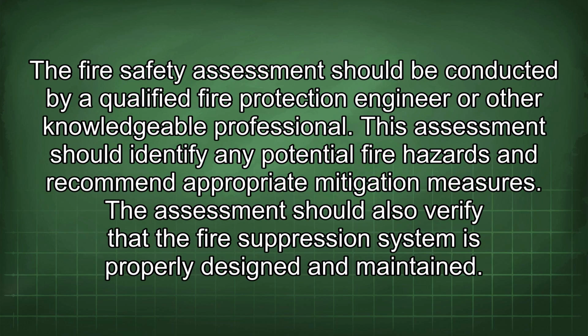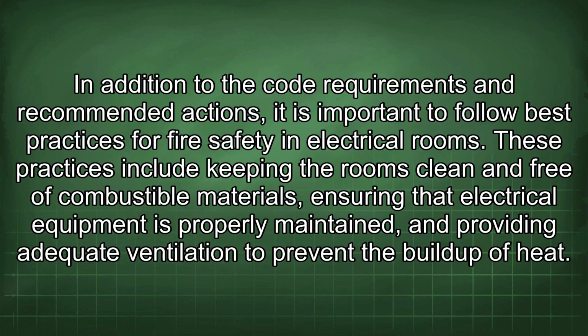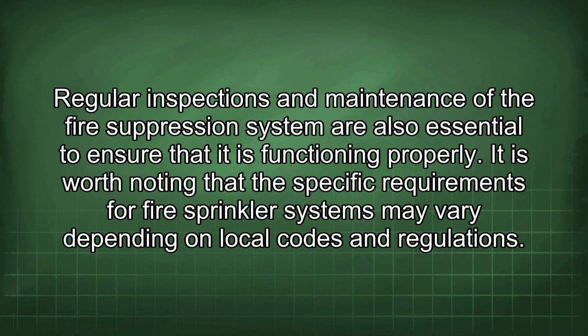Fire safety assessment should be conducted by a qualified fire protection engineer or other knowledgeable professional. This assessment should identify any potential fire hazards and recommend appropriate mitigation measures. The assessment should also verify that the fire suppression system is properly designed and maintained. In addition to the code requirements and recommended actions, it is important to follow best practices for fire safety in electrical rooms. These practices include keeping the rooms clean and free of combustible materials, ensuring that electrical equipment is properly maintained, and providing adequate ventilation to prevent the buildup of heat. Regular inspections and maintenance of the fire suppression system are also essential to ensure that it is functioning properly.